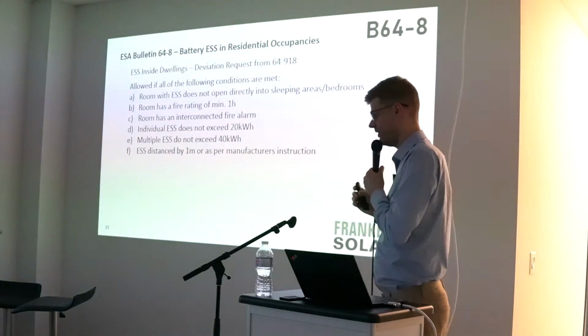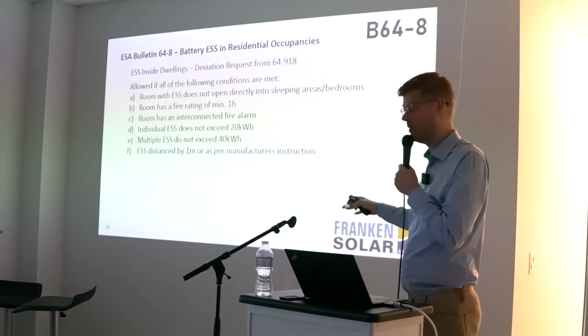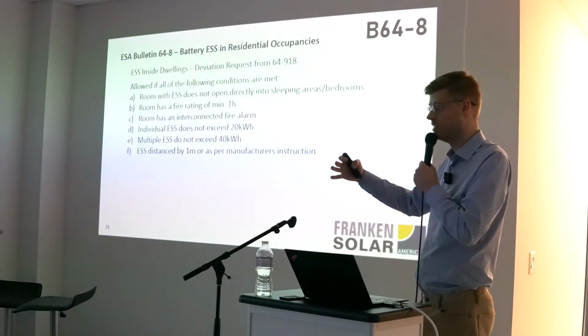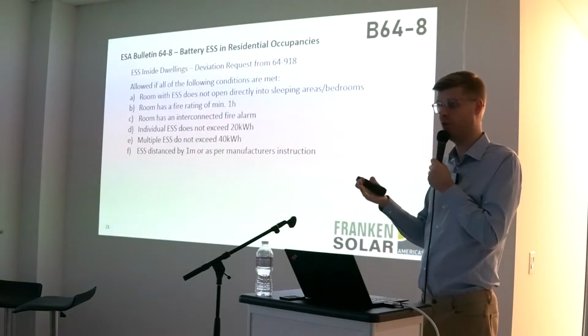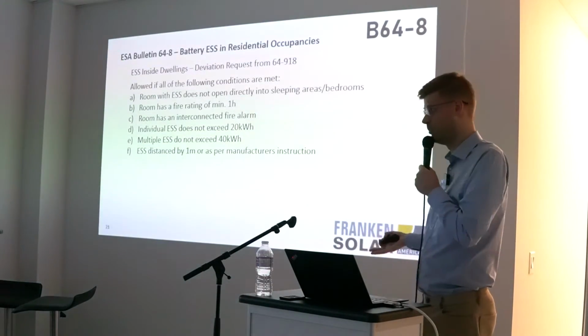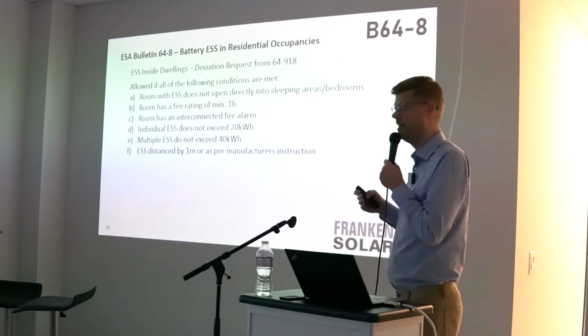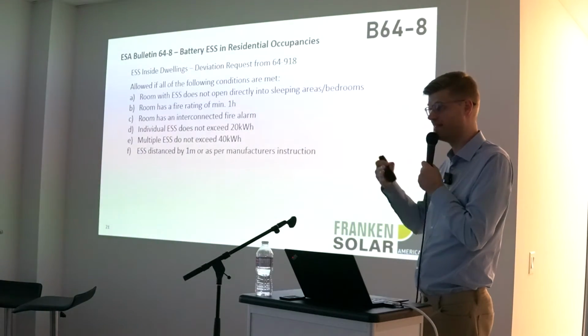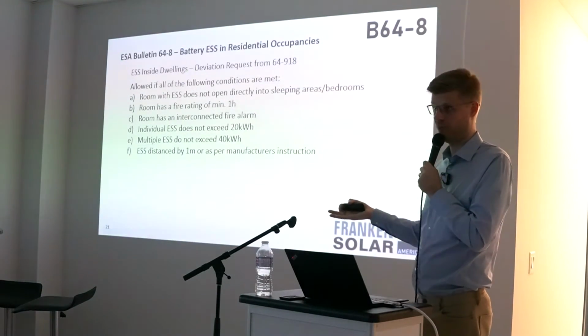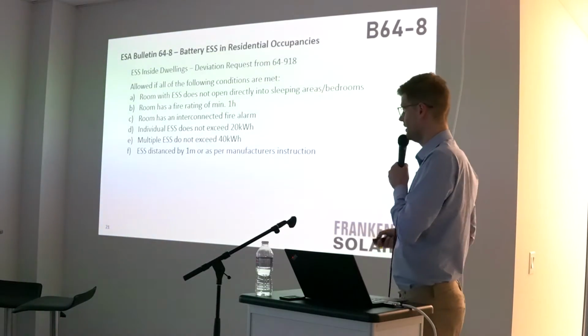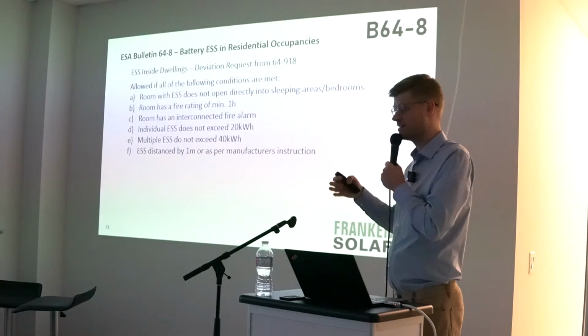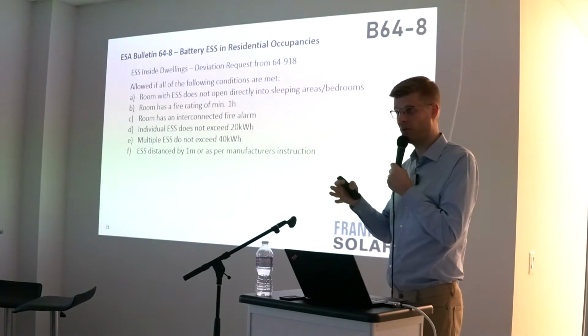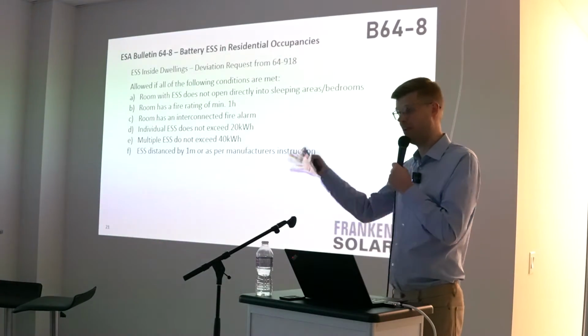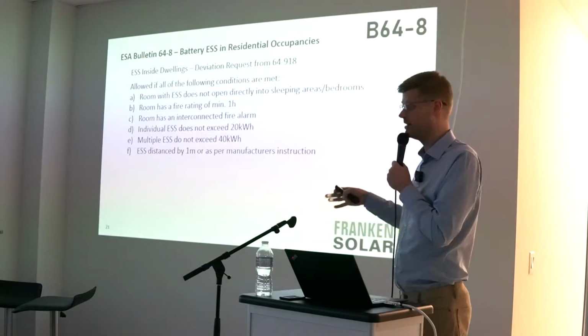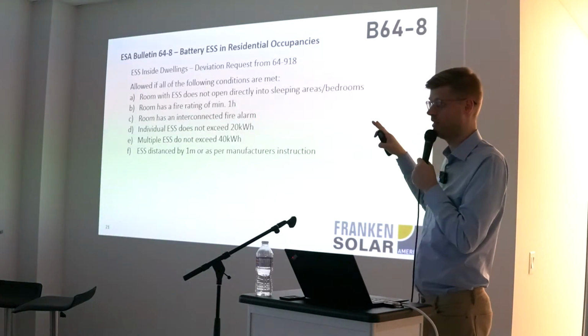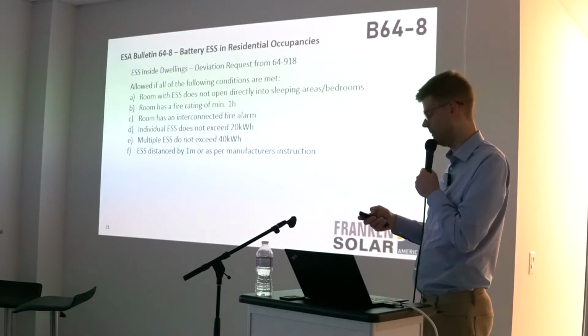Or if the manufacturer specifies and has testing, that they went to a lab and have tested their system at a closer distance. For example, a Tesla Powerwall can be stacked. And lately, there's a special bulletin from Tesla engineering and their lab that you can now actually stack the battery modules back to back, which was not possible just a few months ago because of that testing requirement. Now we can do that, and if any other manufacturer has a test like that as well, that they have one rack with 20 kilowatt hours, and they have tested and documented it with another rack of 20 kilowatt hours, pretty much side by side, then the manufacturer specification and installation instructions will supersede the 1 meter requirement in the code.